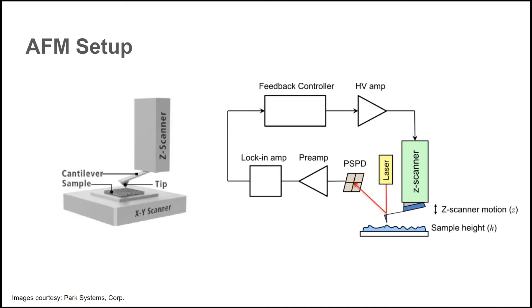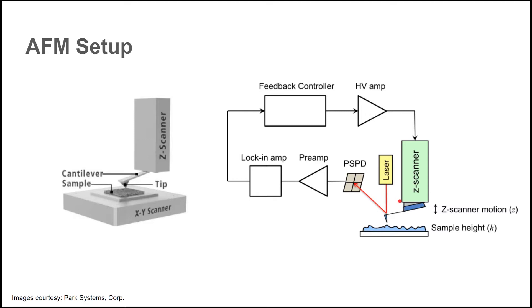Let's turn to some AFM specifics. The hardware components of an AFM consist of a Z scanner, a probe, and an XY scanner. The sample is mounted on the XY scanner, moving side to side. The Z scanner is in a feedback loop. A laser reflects off the probe to the PSPD, the position-sensitive photo detector. The signal from the PSPD feeds back to the Z scanner to control the Z-Piezo. The software will handle much of this feedback loop.